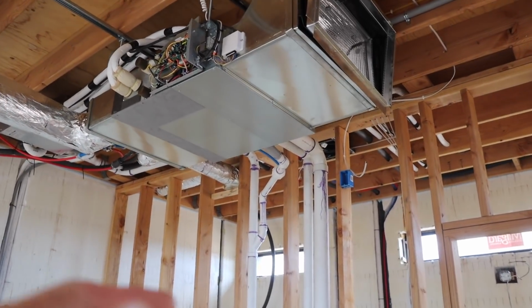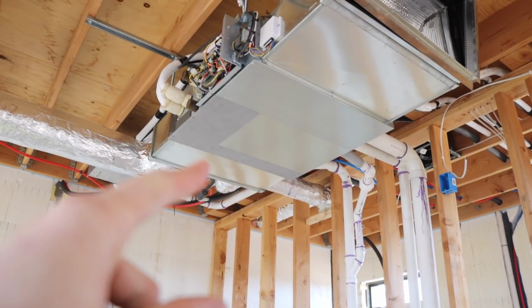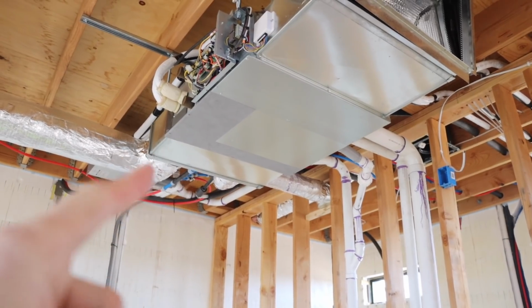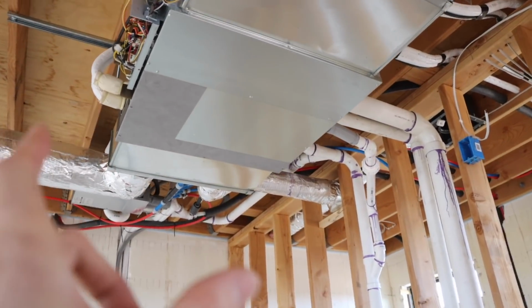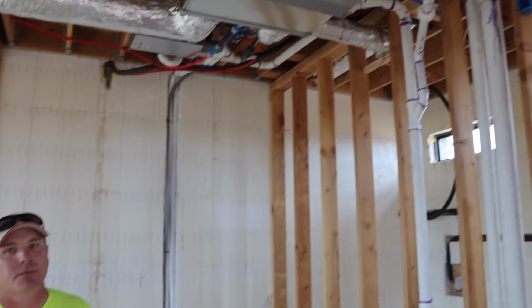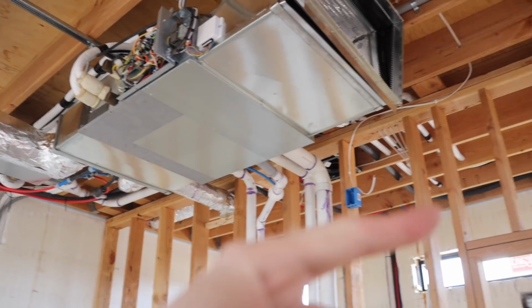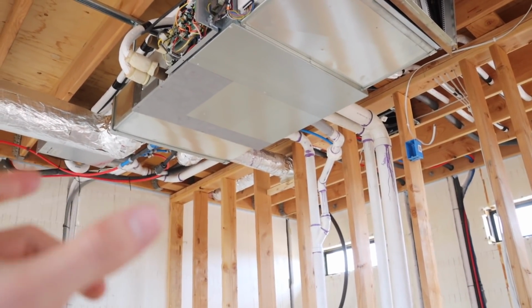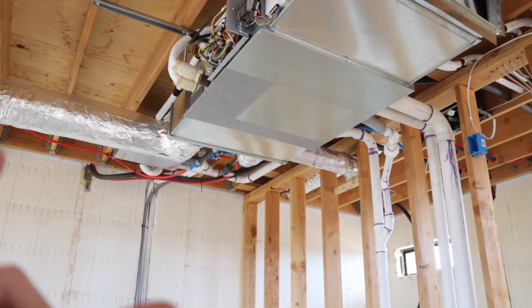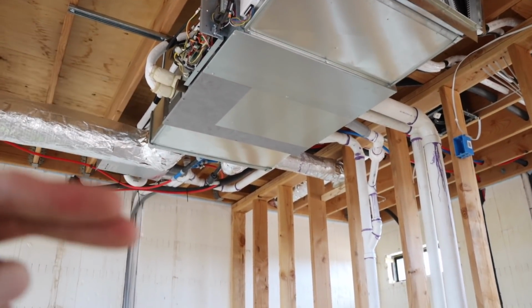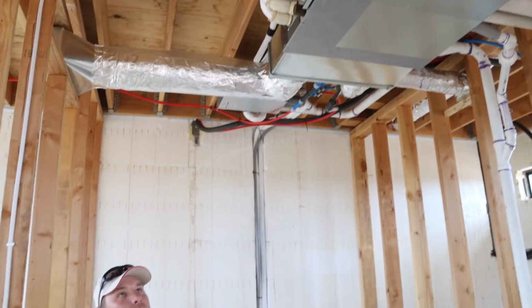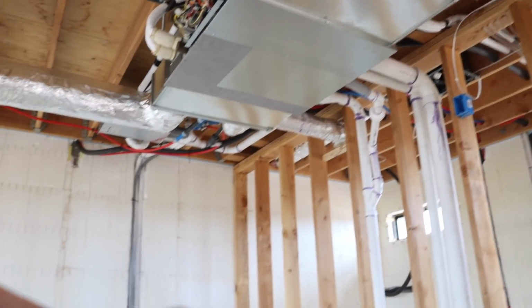So with this system, this would be a better unit for, say, an attic space where you'd have access to it. One important thing with a unit like this is to maintain access to it so it can be serviced in the future if it ever needs it. We're going to do a drop ceiling in this space, like a standard 2x2 grid ceiling, so that we'll always have access to it, but the ceiling will look a lot better than having a big access panel there. That's just something to keep in mind if someone's looking at a system like this.